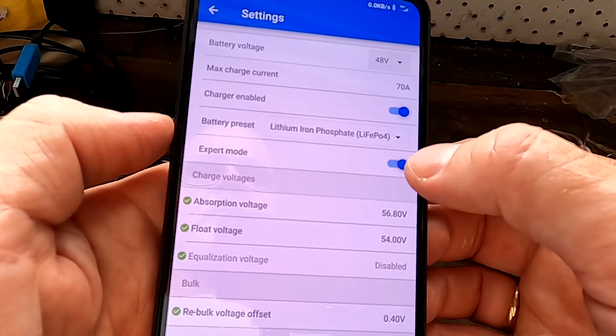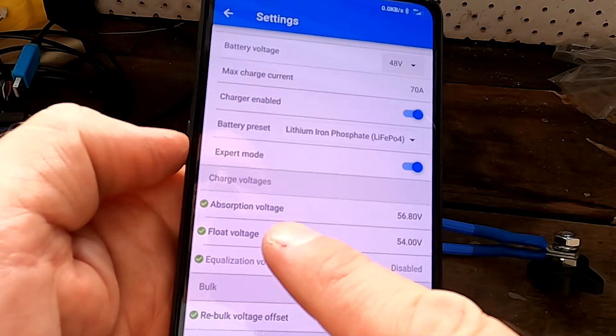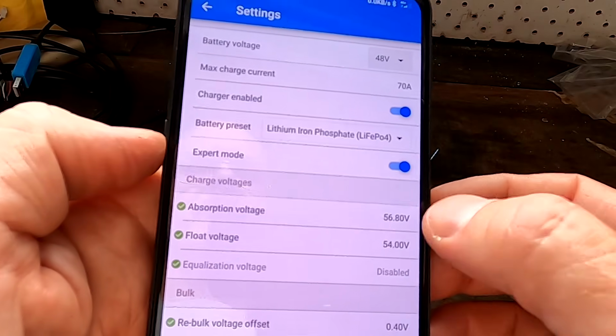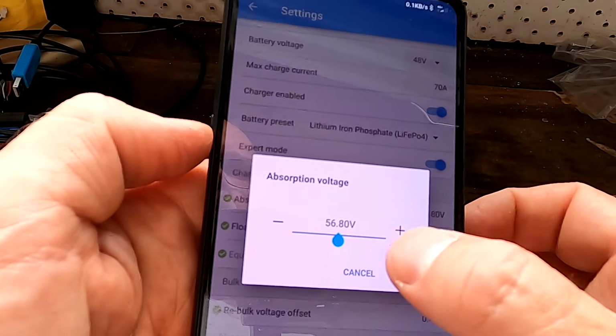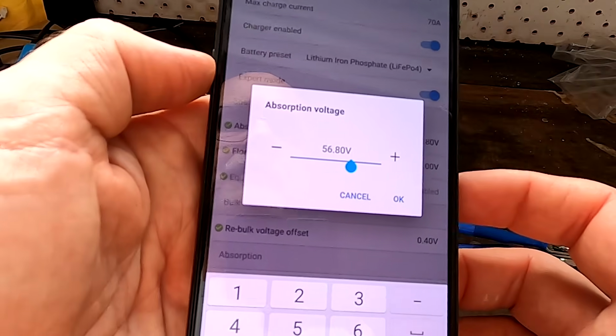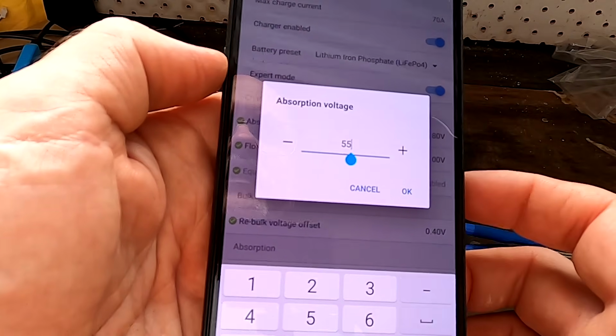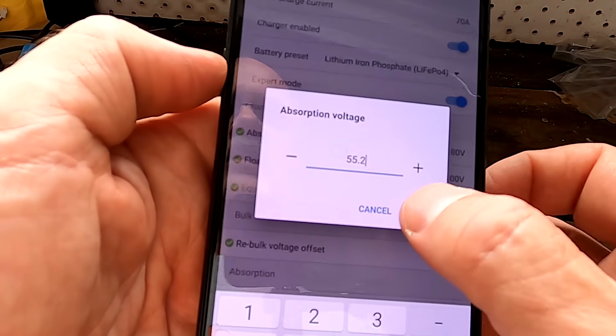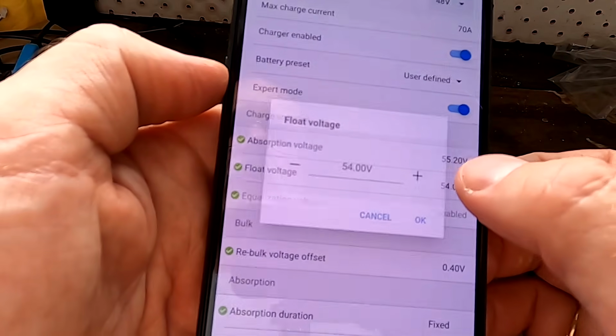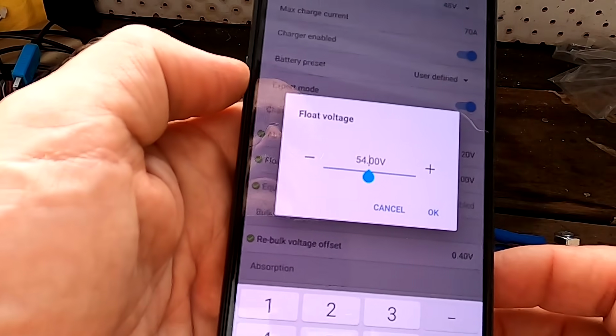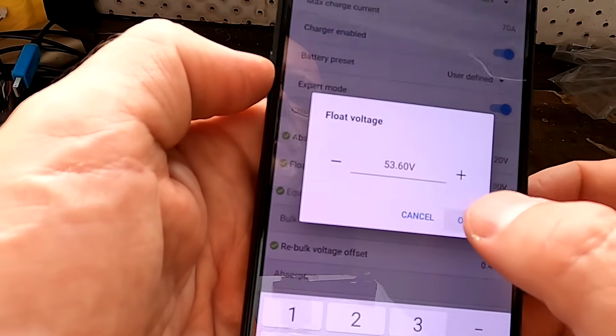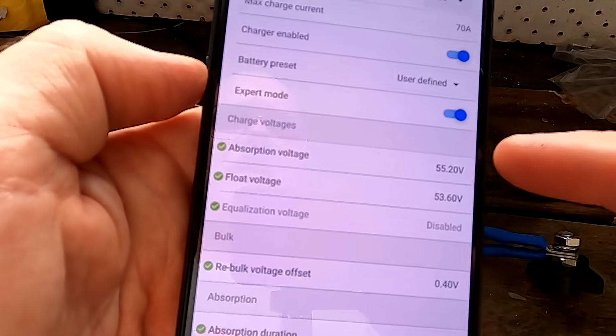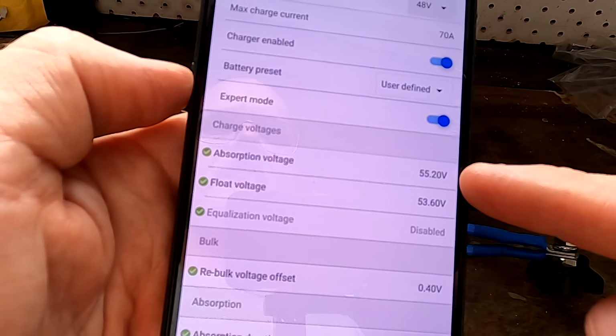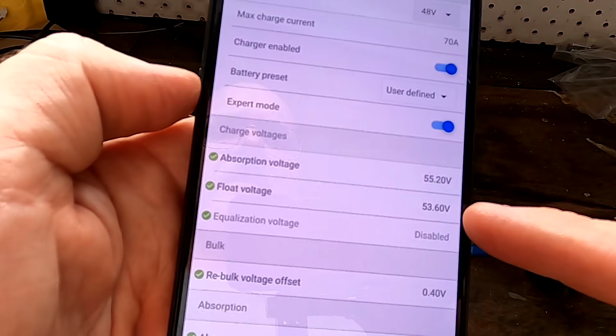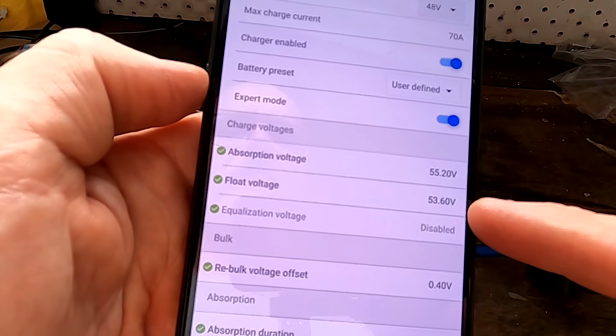So I turn on the expert mode here, and the absorption voltage is usually 56.8, which I think is too high, so I usually set this to 55.2, and the float voltage will be 53.6. So this is 3.45 volts per cell and 3.35 for float.